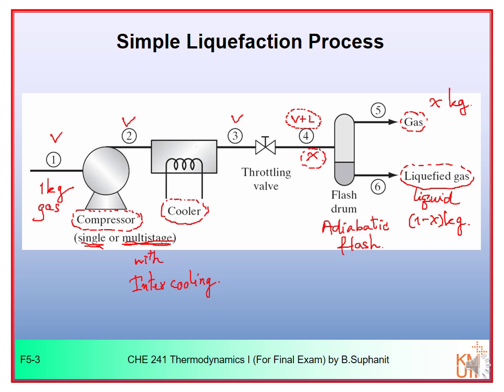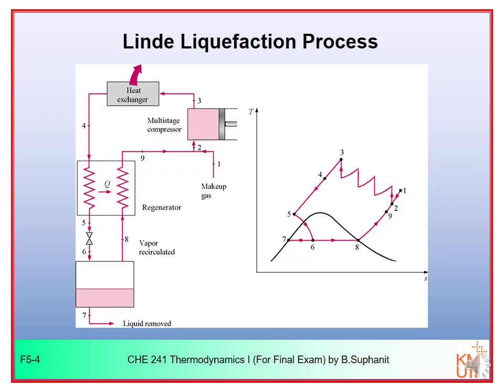We can modify the simple liquefaction system to be more efficient. The more efficient process is called the Linde liquefaction process. In the Linde liquefaction process, we make use of the gas from the flash drum — instead of returning that gas to a storage tank, we use it to cool our compressed gas further.